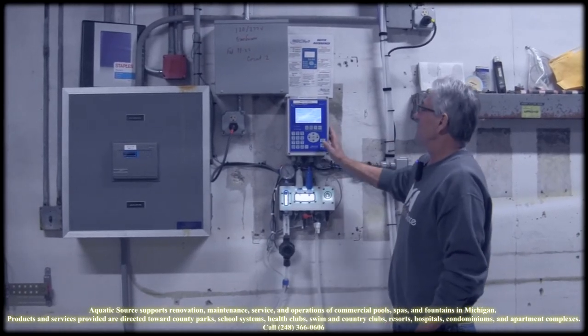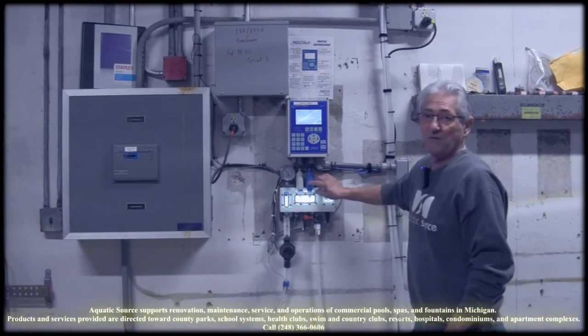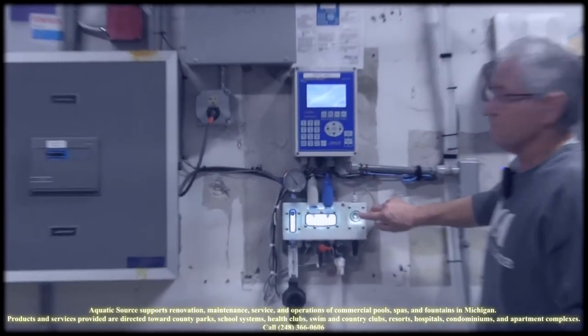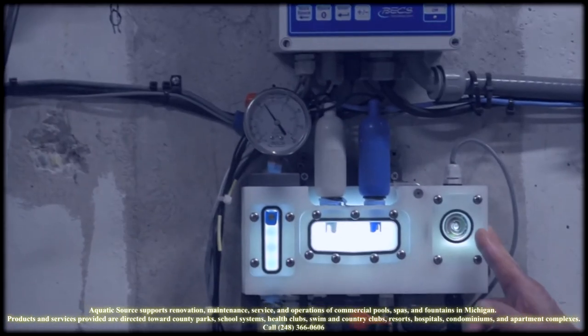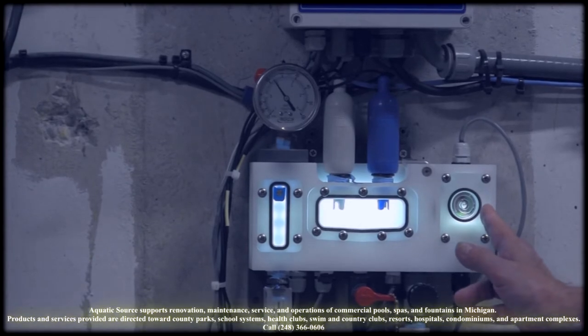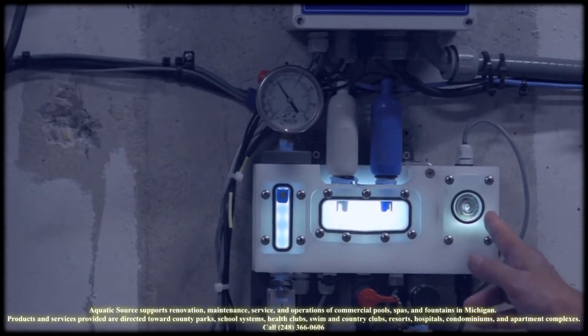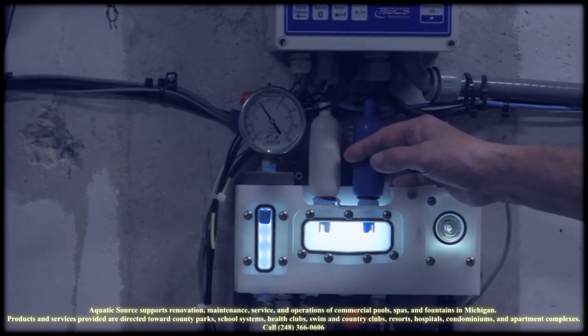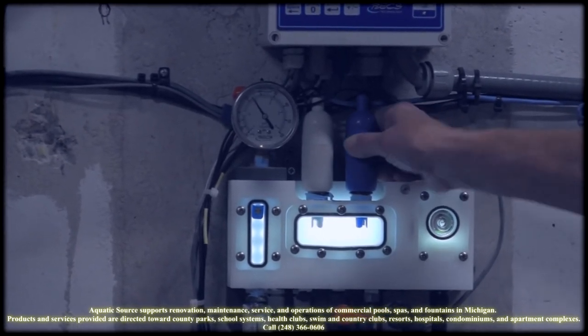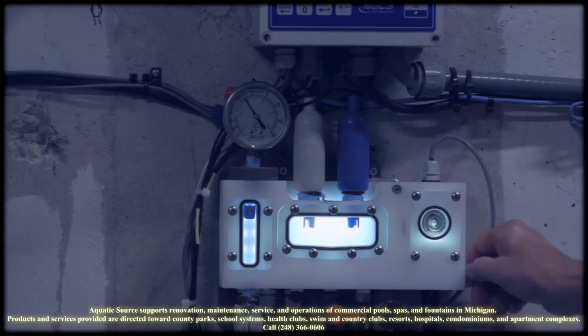Another thing we've got is this unit has an ORP probe, which is how well the chlorine works. But we're also controlling a free chlorine probe, so it actually is calibrated and matches up with your test kit. Where a lot of the other units only use an ORP probe, it's harder for some of your lifeguards to understand how it correlates to your pool.